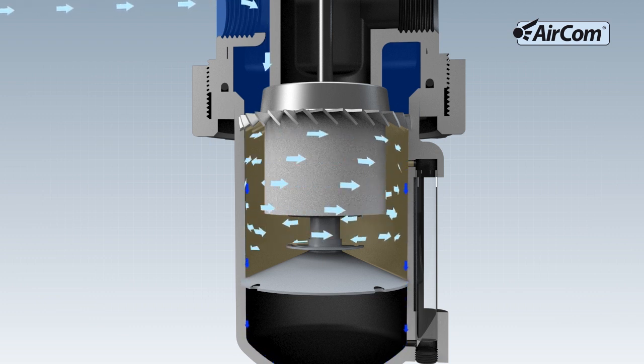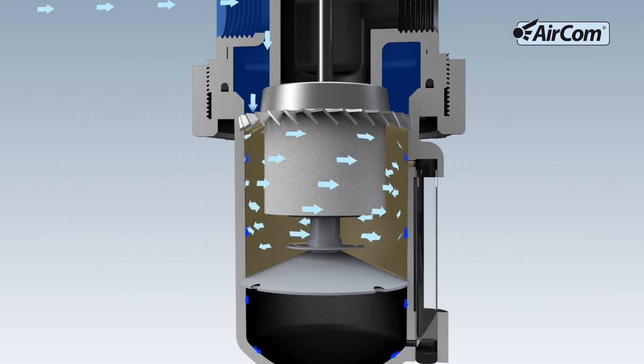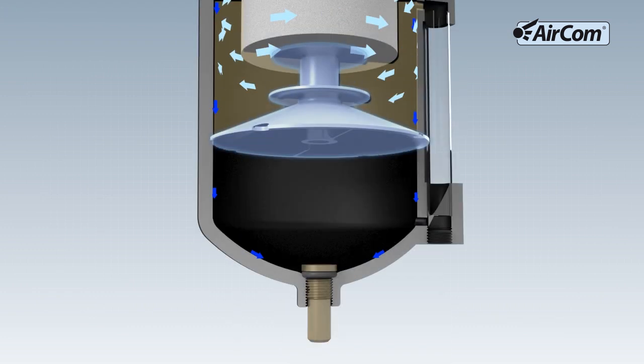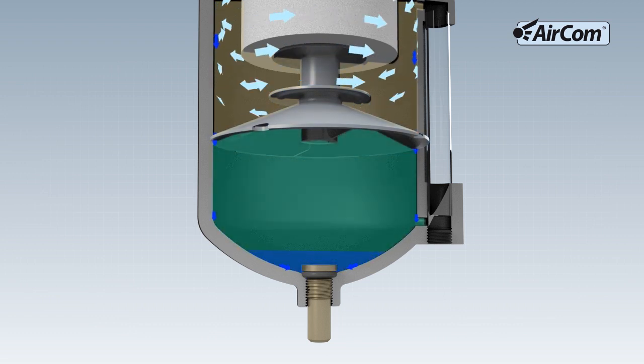The separator disk prevents the collected water, referred to as condensate, being picked up by the airflow again. It divides the filter into a flow zone and a slowdown zone.